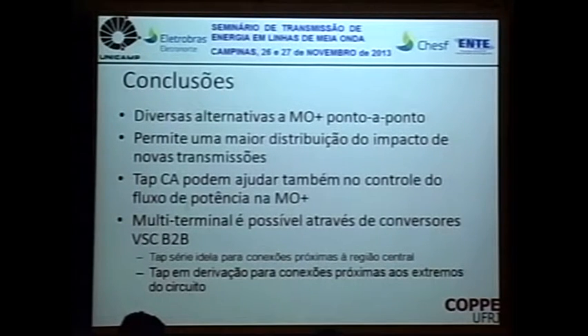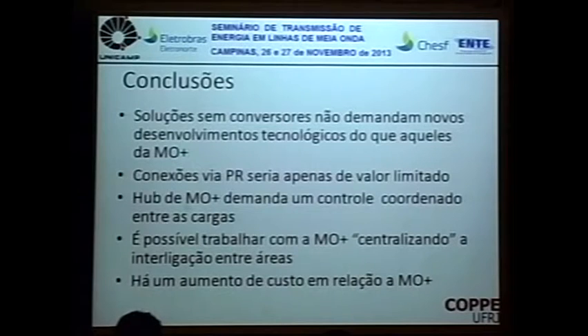As conclusions, we also presented very briefly some alternatives that make the half wavelength a solution that is more than just a point-to-point solution, allowing me to increase the distribution of loads injected in the system. AC tap can help the flow of power, but we're going to talk about this tomorrow. My colleague is going to present this. Multi-terminal can be done as long as we use converters: tap series for connections close to the central area, and tap shunt for connections close to the extremities of the line.